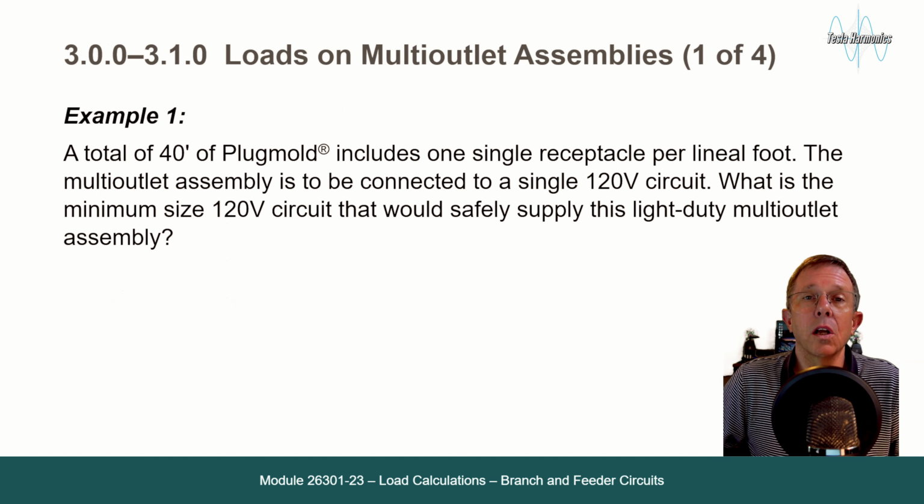Example 1, Loads on Multi-Outlet Assemblies. A total of 40 foot of plug mold includes one single receptacle per lineal foot. The multi-outlet assembly is to be connected to a single 120 volt circuit. What is the minimum size 120 volt circuit that would safely supply this light duty multi-outlet assembly?